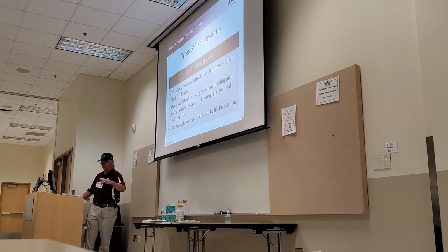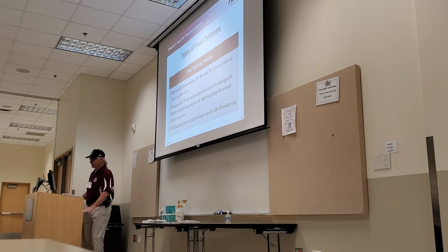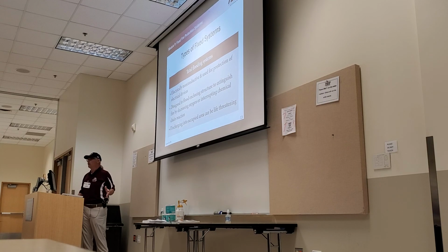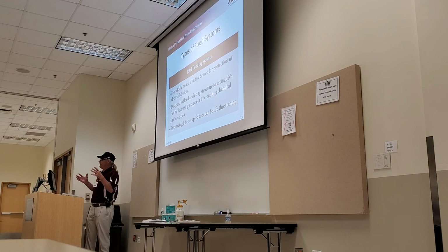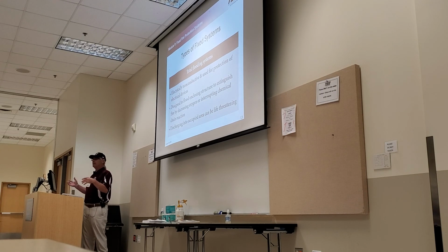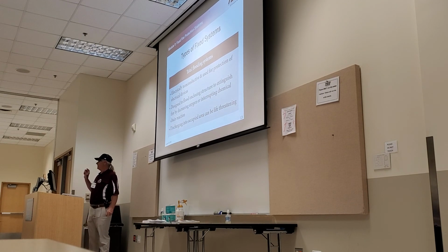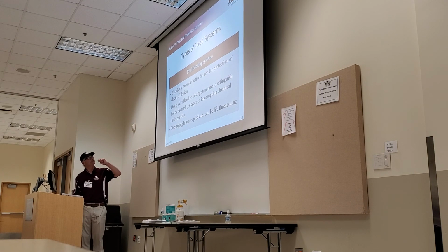But it fills up fast. If there's a cloud, it starts at the bottom, and you only have to take 2 breaths and it's on. So we put a time delay on that. When the fire alarm panel detects the flames and trips the system, those sirens and horns and lights go off for between 10 and 60 seconds to give people time to get out, and they have to measure that. And then the CO2 completely fills up the place.